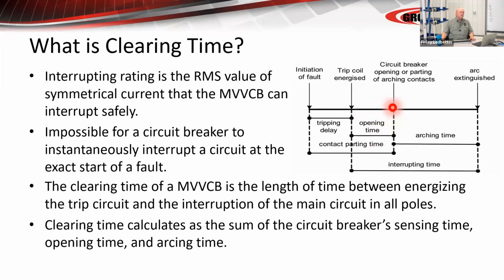So basically, this is parting time. From here to here gives you the parting time. Most timers that you use today to determine the mechanical health of your circuit breaker measure parting time. Beyond that, there's velocity and speed, there's contact bounce, all sorts of things that come into play. But basically, if your parting time is good, we've learned that it's going to run close to speed and velocity. Bounce is another story. So most people just test for parting time. That does give you a good, valid test and a real indication of the lubricant and your maintenance interval. So if those parting times are going up, which they will start doing after about 5 years, you need to know that.